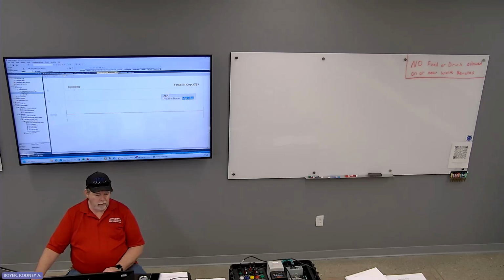So, under the task you have the program, and under the program you have the routine or routines, depending upon which one you're talking about. The main routine is always automatically scheduled, and then for any subsequent subroutines you have to put in a jump instruction.